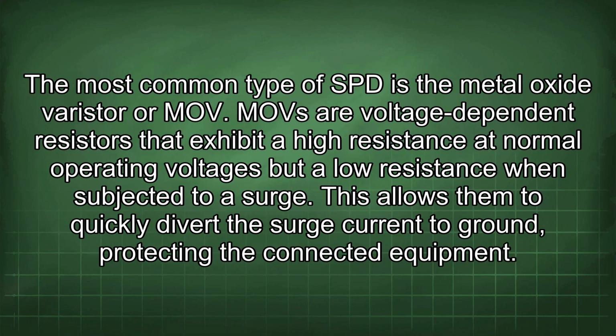The most common type of SPD is the metal oxide varistor, or MOV. MOV are voltage-dependent resistors that exhibit a high resistance at normal operating voltages but a low resistance when subjected to a surge. This allows them to quickly divert the surge current to ground, protecting the connected equipment.